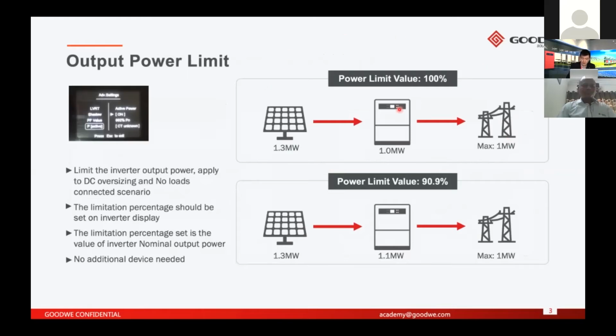So you can see the panels connect to the inverter, which connects to the grid. So there's no load consumption between the inverter and the grid. If you want to limit the power from the inverter, you can use the output power limit. In this example, the PV module's capacity is 1.3 megawatt, and the inverter capacity is 1 megawatt, and the maximum you can output is 1 megawatt to the grid.